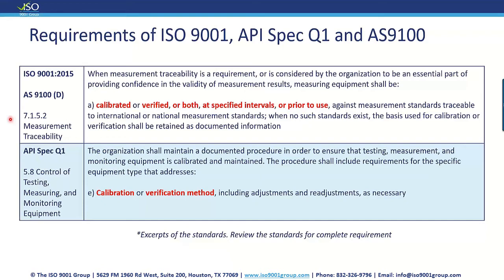It actually doesn't say annual. So a lot of companies just do it annually, just, I guess, because they get in the habit of doing that annually. And of course, calibration companies love you for doing it annually. That's some revenue that they can count on every year. But really, you should look at it from the perspective of what the OEM requires. All right, but a lot of people interpret that to be on an annual basis, so no problem. Or it says, or prior to use. So prior to using the device, right? So you can see a lot of options there. Now, it says, against measurement standards traceable to international or national measurement standards. When no such standard exists, the basis used for calibration or, again, verification shall be retained as documented information.